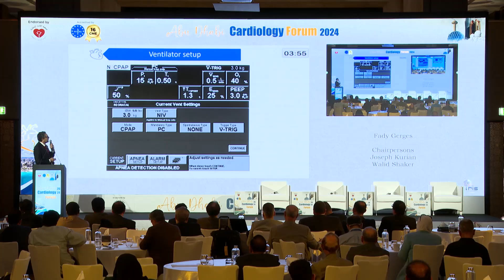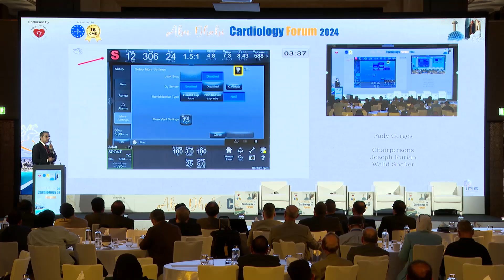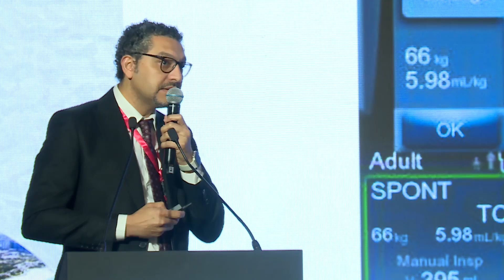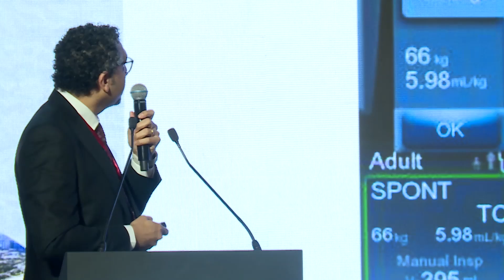So one more thing as well is the settings. So you don't have to go all through the settings, but there's something very important. Can you see this S? When you see that patient and you're putting a CPAP, S means spontaneous breathing. So a red S means that the patient is spontaneously breathing. If you didn't see that S, that means there's something wrong. And anyway, the ventilator will just make an alarm and will tell you that the patient is apneic.